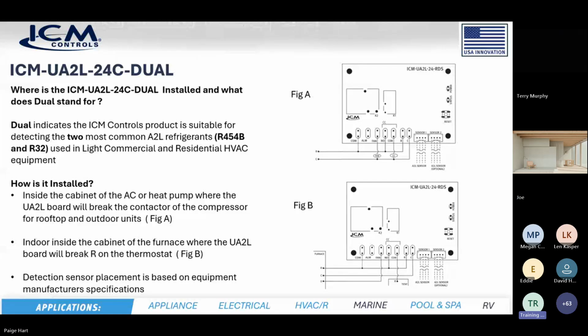So here, you can see the difference. We've got the furnace port over here. We've got the R, the C, and the G connected to the board. So basically, the board is being powered by the furnace port, okay? And if you sense a leak, what it's gonna do now is break the R of the thermostat. This is gonna shut the call up from the board. So basically, your furnace is gonna say, oh, I have no W call, and it's gonna shut the gas off. And this relay will energize the G terminal, which is the fan terminal of your control board. So it'll run your indoor fan to mitigate, keep air flowing, okay? So that you don't have a buildup of any gas.